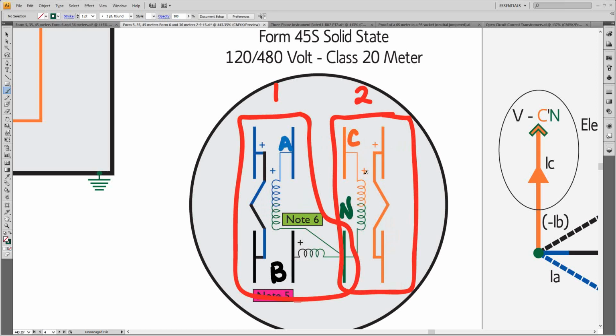Same potential that was across the 5S had C to neutral across it. The 35S had C to neutral across it. The 45S has C to neutral across it. So this element in all 3 meters is wired exactly the same, and so it's not the effect here that we're worried about. It's with the 35S, they doubled the voltage across this potential coil. In this one, as I plug this one in, B phase voltage has a place in this one. And so we're not going to multiply anything in this one. We're going to measure A to neutral voltage across my first potential coil. Again, solid state meters that have auto-ranging coils in them have to have a tie with all the potential coils to one point. So A to neutral across one.